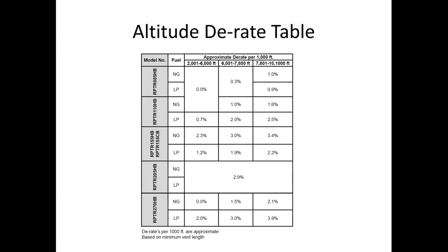The Sage 2.3 platform that we're using has everything in there. The altitude settings, the LP settings, whether it be sea level or whether it be at 10,000 feet. One control and one display will fit the entire product line. The displays are also backwards compatible to the first generation Raptors. The first generation Phantoms, unfortunately, the Sage 2.3 control is not backwards compatible to the first gen Phantoms.